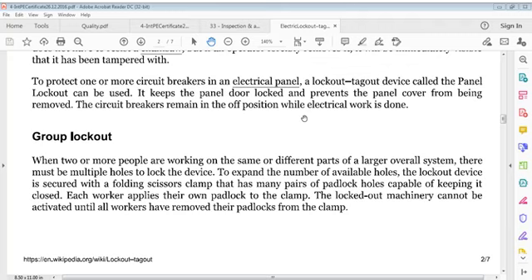Once again, when two or more workers work on the same or different parts of a large overall system, there must be multiple holes to lock the device. Expand the number of available holes. The lockout device is secured with a folding scissor clamp that has many pairs of padlock holes capable of keeping it closed. Each worker applies their own padlock to the clamp. Locked out machinery cannot be activated until all workers have removed their padlocks from the clamp.